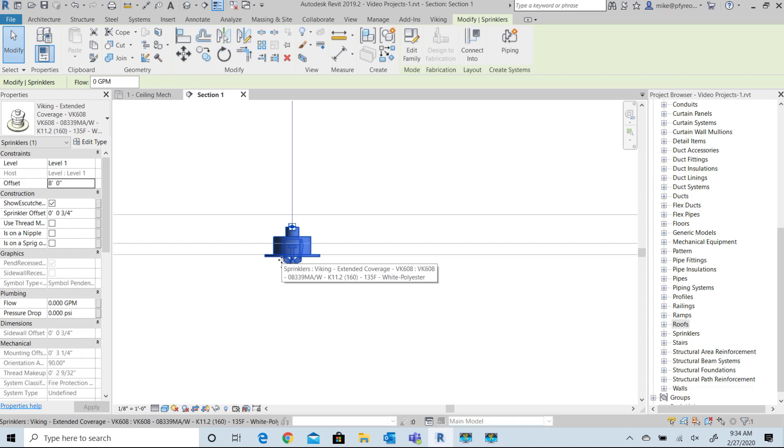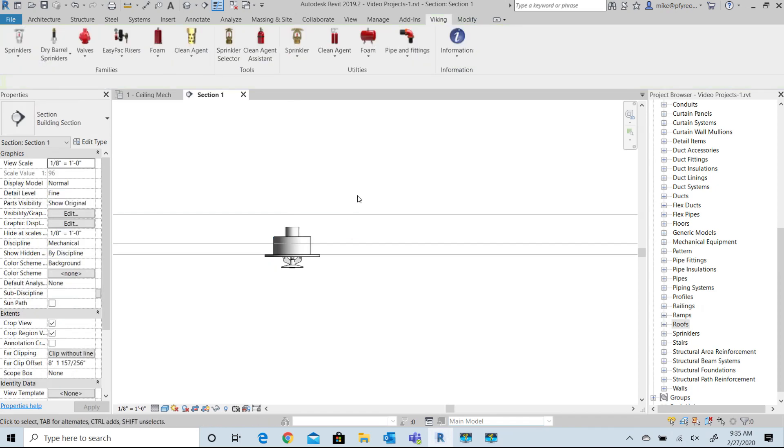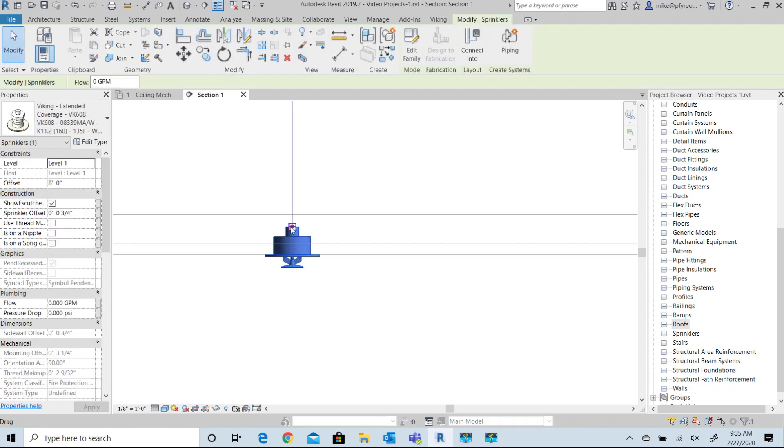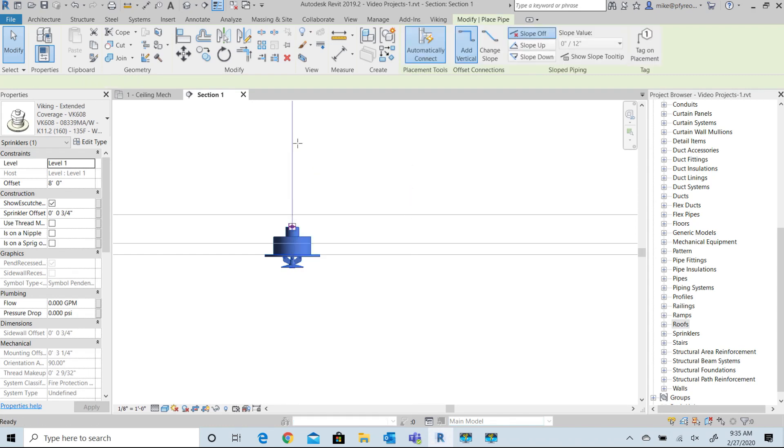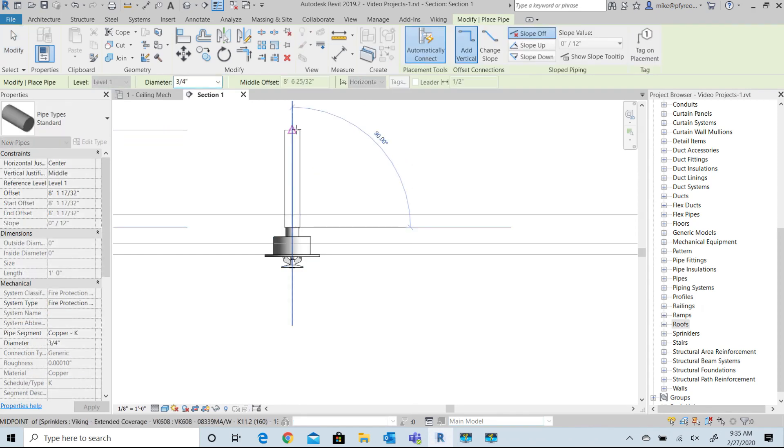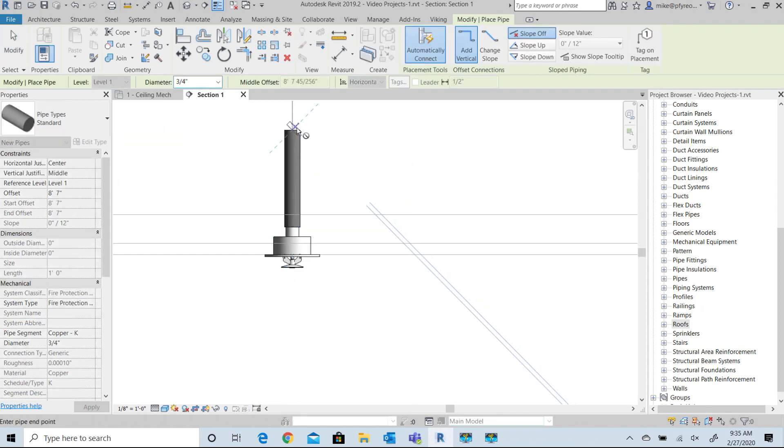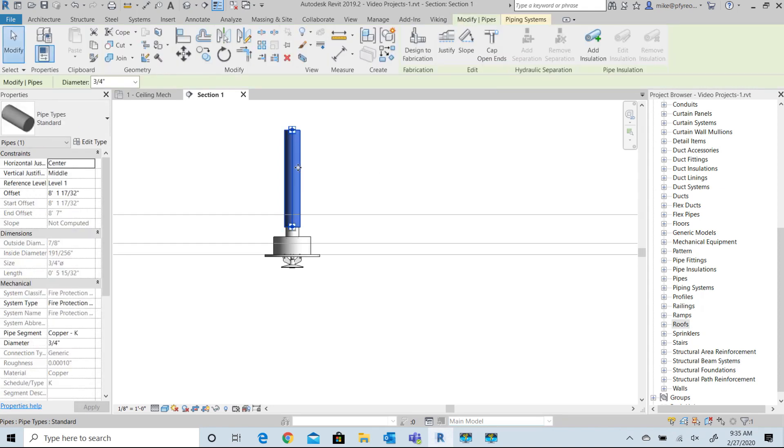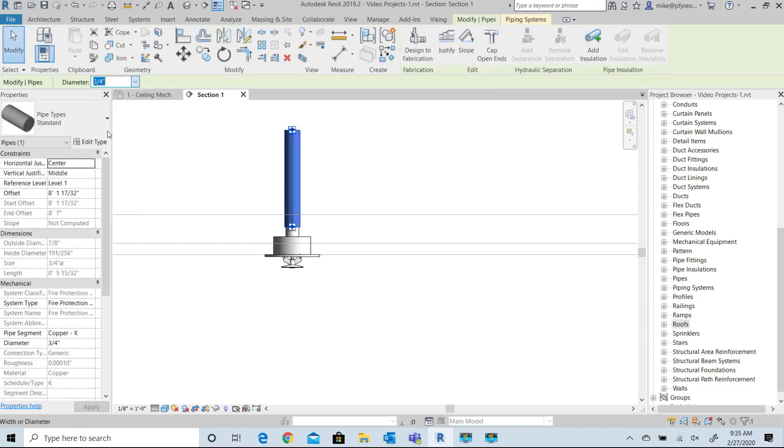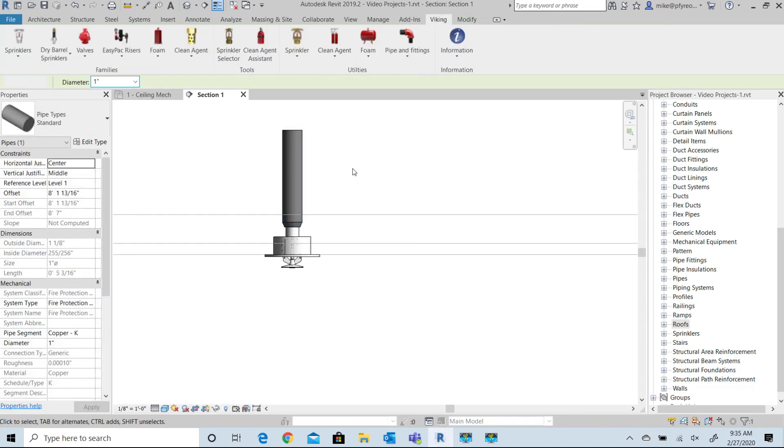If the ceiling height changes, for example, from eight foot to nine foot, you could just change that offset value to nine foot and you'll still have the same adjustment value of the half inch or three quarter inch adjustment to the deflector below the ceiling. That doesn't change.